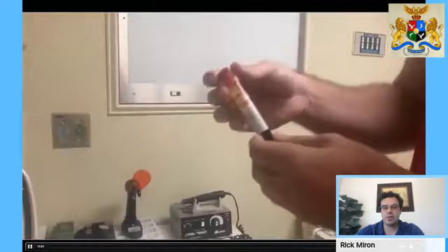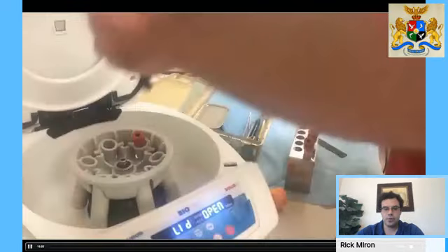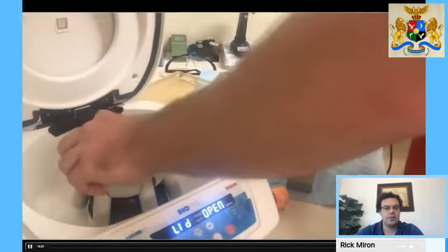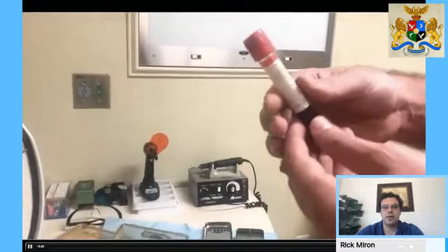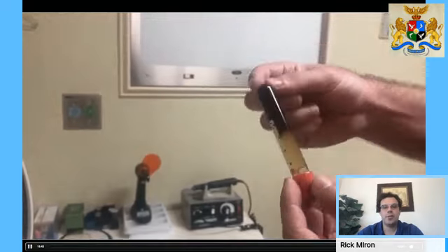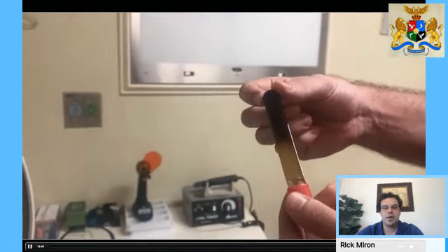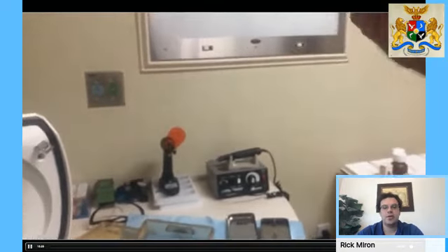I want to show you guys the results here. Okay, at the very end of this video, after the spin cycle, I'm now taking out the tubes, and watch what you'll see here. When you spun using the newly designed hydrophilic tubes, have a look at this. 8-minute spin cycle on a horizontal centrifuge, you can take the tube and put it directly upside down. It's fully clotted, okay? That's not because it's my blood, it's only because of the hydrophilic surface of that tube.